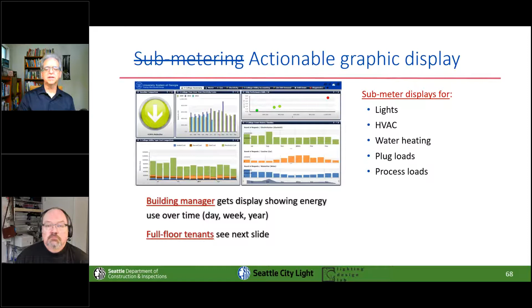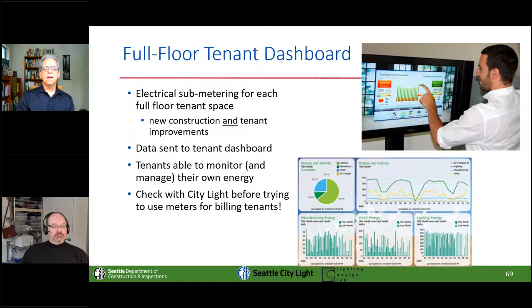All right, so I wanted to touch on metering, and I wanted to emphasize that it's not the meters that I care about, it's the display that the building manager can see every morning. Seattle rules haven't really changed much, but the state code now requires all 5 of those sub-metering categories instead of just HVAC and hot water like they used to. So whenever you've got a tenant that takes up a whole floor or several floors in a multi-tenant building, that tenant gets its own dashboard. The idea is that the landlord can't typically do much about tenant energy use, but the tenants might want to track this themselves. I certainly know that at the last firm I worked at, they would have had a whole committee walking around with clipboards, checking to see if you had things plugged into the right thing.